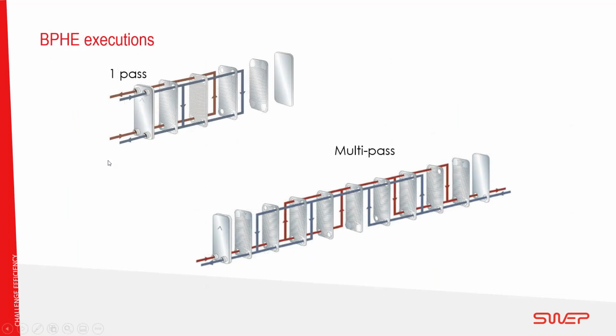So we talk about different executions with heat exchangers. There's a lot of different executions. I'm just going to cover the two basic ones here. The first one is what we call single pass, and this is what we would commonly see inside, say, a gas boiler, for example. By single pass or one pass, hopefully you can see my mouse pointer here, if you see the blue channel going in through the connections, you'll see it dropping down, and then the hot side is going up in the opposite direction. So the two different medias are just passing each other once, and that's allowing the transfer of energy.